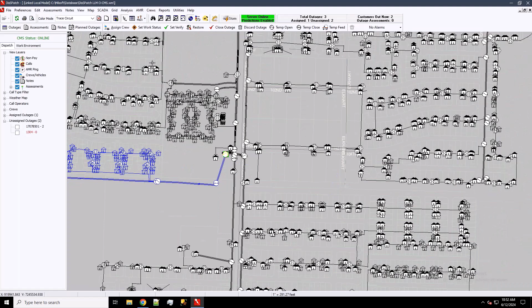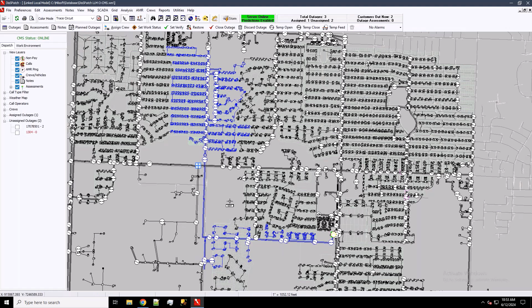So the scenario we're going to demonstrate is an automated restoration scheme. We have this breaker locked open. The next thing we're going to see is that we automatically open a normally closed switch, and then close the normally open switch, backfeeding a portion of these customers and automatically restoring a section of this outage. I'll zoom in here just a little bit to make that easier to see, and we will step through this next demonstration. So Brett, when you're ready, we're going to send an open on breaker 3, an open on the first switch.